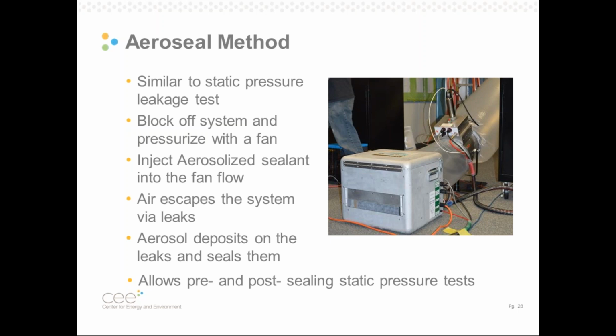And then you use their fan box to pressurize this portion of ductwork. The difference is that in addition to this fan box, there's also an injection system downstream. And that system injects this aerosolized sealant into the fan flow. So now the fan is pressurizing the ductwork with this flow that's laden with the aerosol sealant. And as air escapes through the leaks in the ductwork, that sealant deposits on the leaks and builds up on itself and slowly seals them over time. So pressure builds up, and one of the nice things is you essentially watch the sealing in real time.